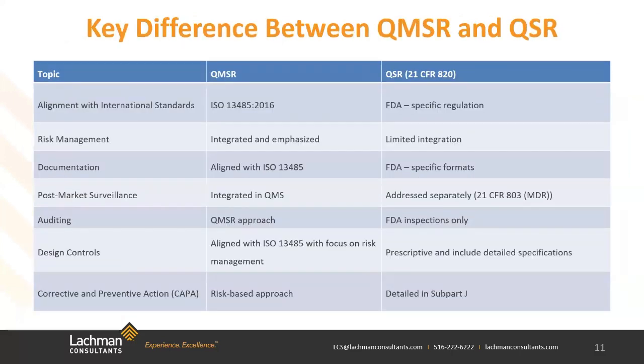Now that we talked a little bit about the inspections, we're going to talk a little bit about the differences that we are seeing with regards to the QMSR and the QSR. The quality management system regulation and the existing quality system regulation differ primarily because the QMSR aligns with the international standard ISO 13485, which again is FDA's effort to harmonize requirements with global quality management practices for medical devices. However, some of the key differences that I'm going to point out here with regards to alignment with international standards: as we know, the QMSR aligns with ISO 13485, whereas the QSR is FDA-specific regulation developed independently of the international standards. We've talked already a little bit about risk management, but here we go again.